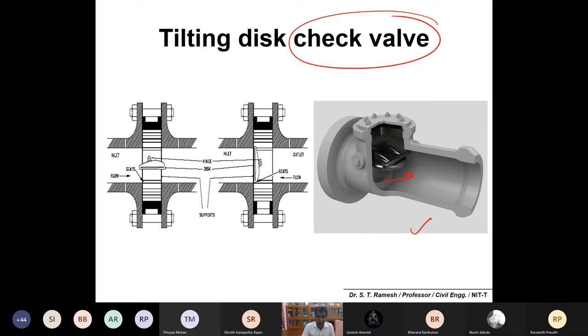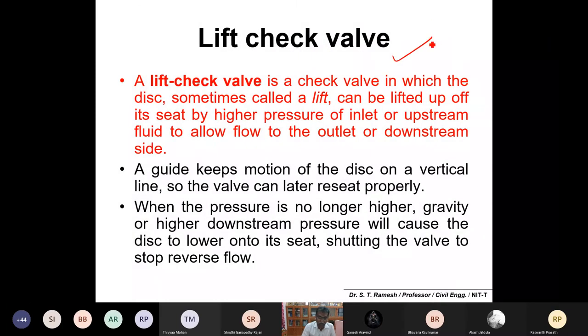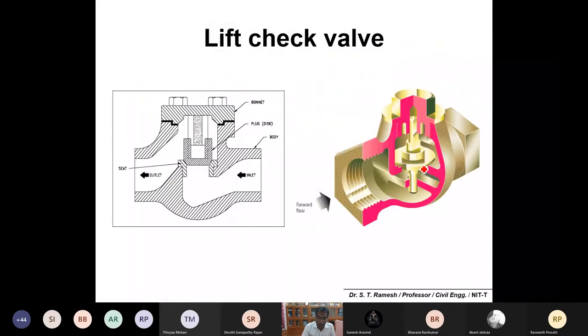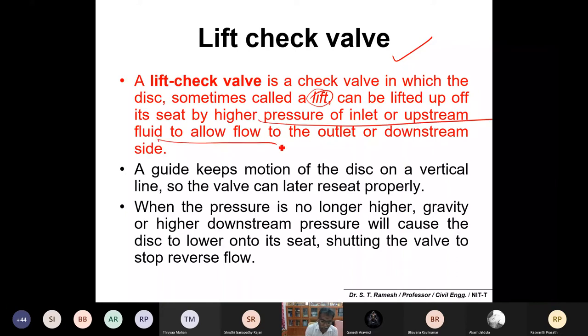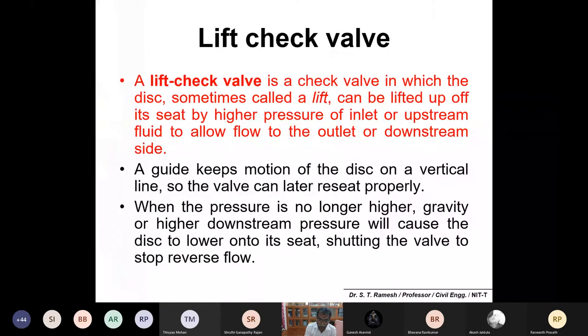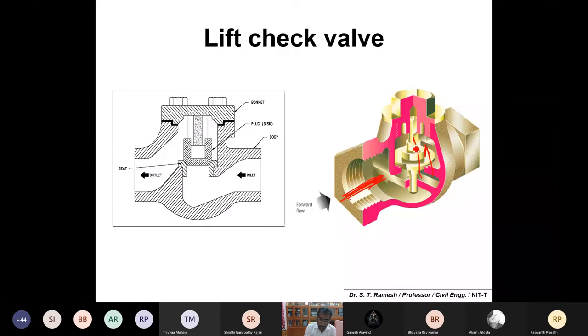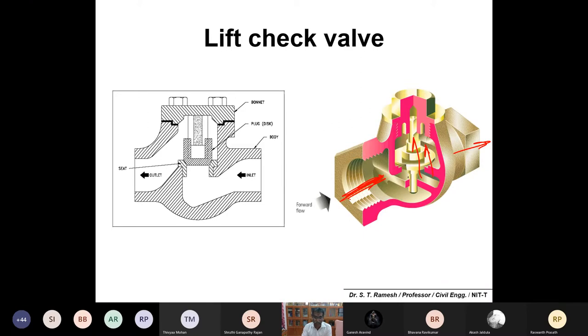All check valves will allow only one direction of flow and will not allow return flow back to the system. You can also have a lift check valve. If there is considerable pressure, the disc automatically shifts from one position to another. The lift check valve is a check valve in which the disc — sometimes called a lift — can be lifted off its seat by higher pressure of the inlet or upstream fluid.